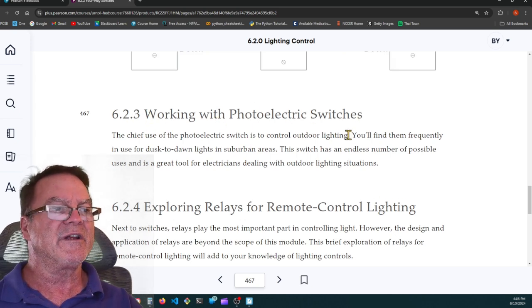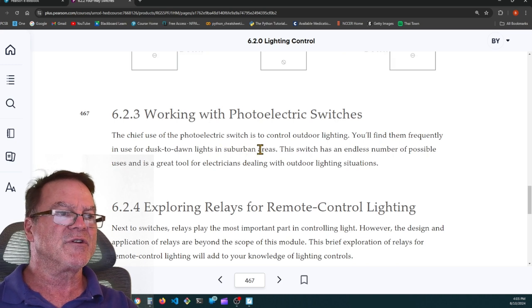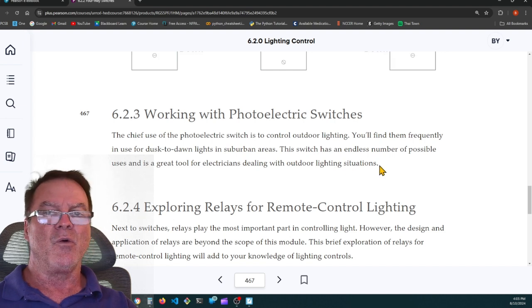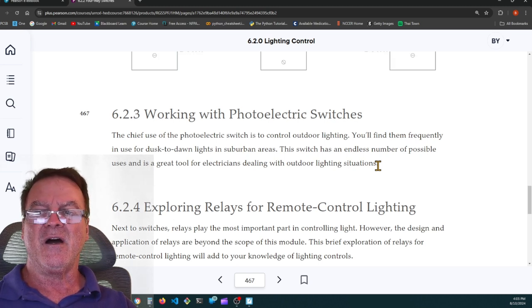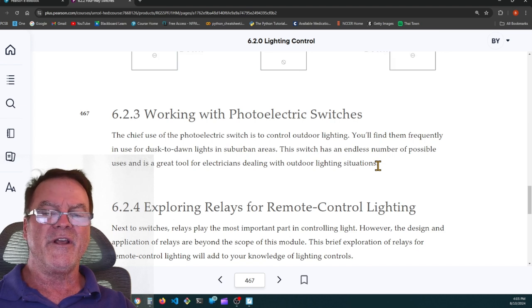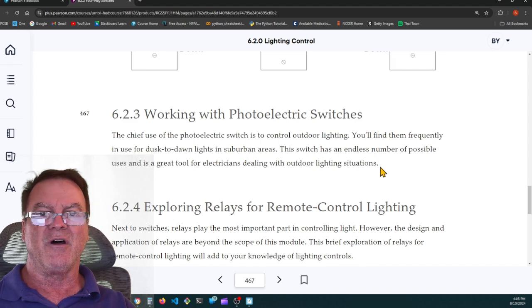6.2.3, working with photoelectric switches. The chief use of the photoelectric switch is to control outdoor lighting. You'll find them frequently in use from dusk to dawn lights in suburban areas. This switch has an endless number of possible uses and is a great tool for the electrician dealing with outdoor lighting situations. So this can turn the light on when the sun goes down and it gets dark. It'll turn the lights on and they'll stay on until dawn, till morning when the sun starts to come up. It'll sense the presence of light and it'll turn off the lights.